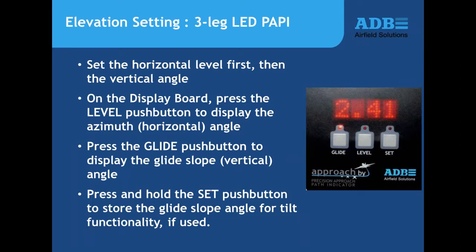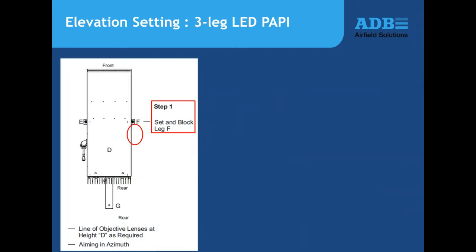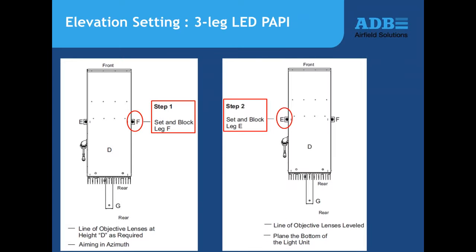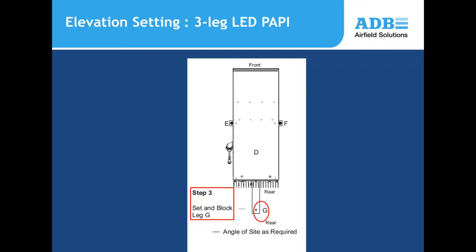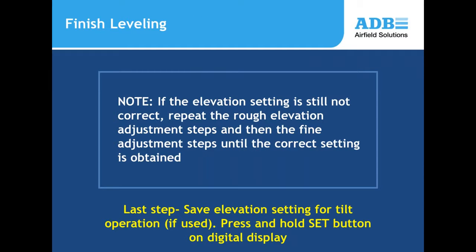For each unit, adjust the front two legs first to achieve horizontal level — reading zero degrees on the horizontal measurement. Then adjust the rear leg to achieve the correct vertical angle for that light unit. Once the measurements look correct, lock everything down. In the FAA market where tilt switch functionality is used, press and hold the set button to store those values in the control board so the system knows when the unit is out of alignment.